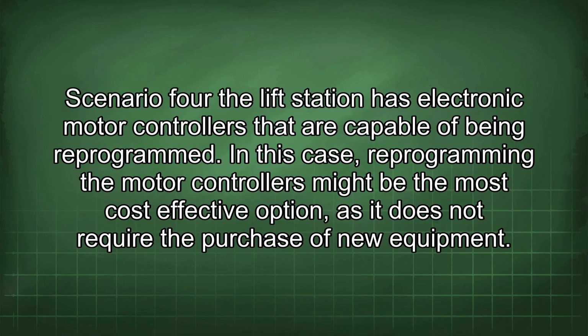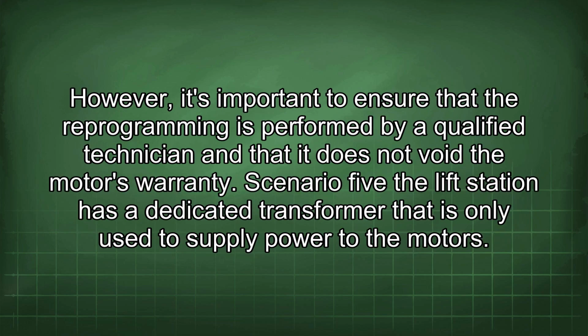Scenario 4: the lift station has electronic motor controllers that are capable of being reprogrammed. In this case, reprogramming the motor controllers might be the most cost-effective option, as it does not require the purchase of new equipment. However, it's important to ensure that the reprogramming is performed by a qualified technician and that it does not void the motor's warranty.